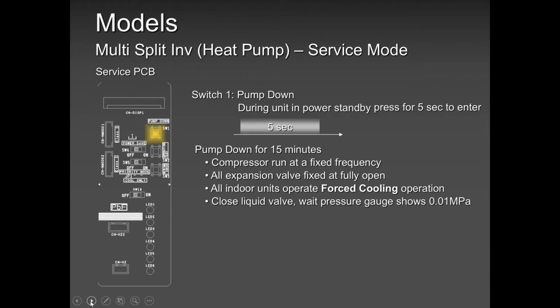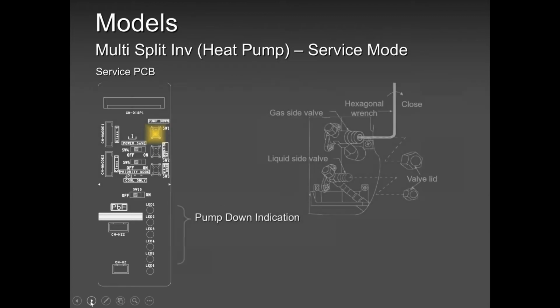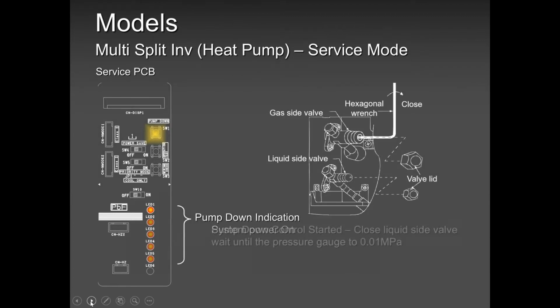By then you have already closed your liquid line. Now you're waiting for the gauge to get closer to 0 before you shut your suction line. Okay, guys? Those indicators will tell you how much time you have left. Three lights blinking tells you have 3 minutes. 2 lights blinking, you will have 2 minutes. 1 light blinking, 1 minute, and now you are ready to close your suction line or your gas line.